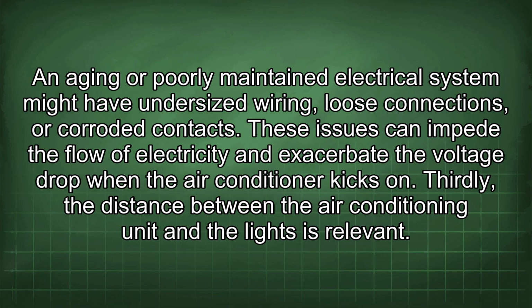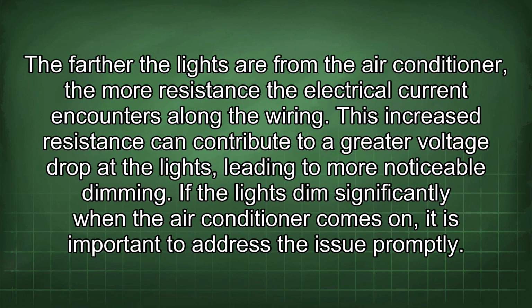Thirdly, the distance between the air conditioning unit and the lights is relevant. The farther the lights are from the air conditioner, the more resistance the electrical current encounters along the wiring. This increased resistance can contribute to a greater voltage drop at the lights, leading to more noticeable dimming.